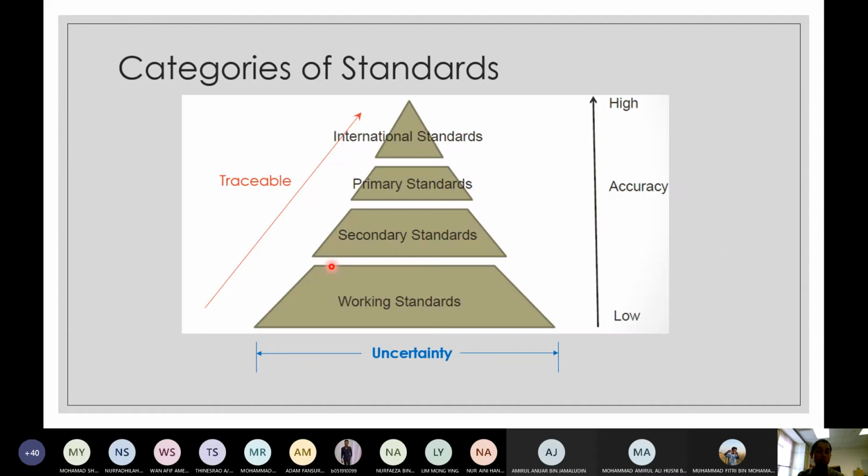Now if I go back to the triangle, you see the sequence. Working standards at the bottom: from time to time you calibrate your equipment with reference to the secondary standard. The secondary standard, from time to time, needs to be calibrated with the primary standard. And the primary standard, from time to time, needs to make sure that its equipment follows the international standard. This sequence from bottom to top is what we call traceability, the ability to trace a certain measurement from the lower level up to the highest level.